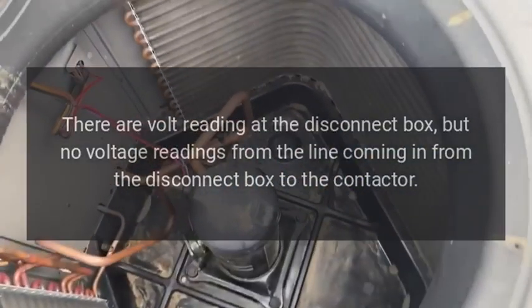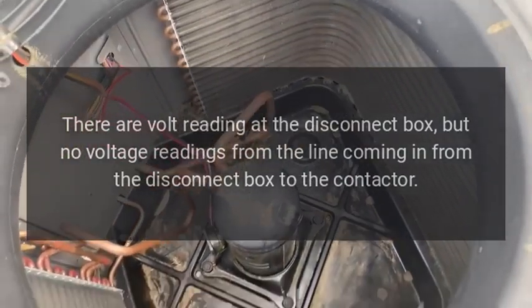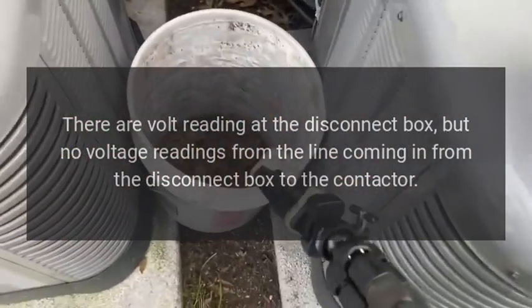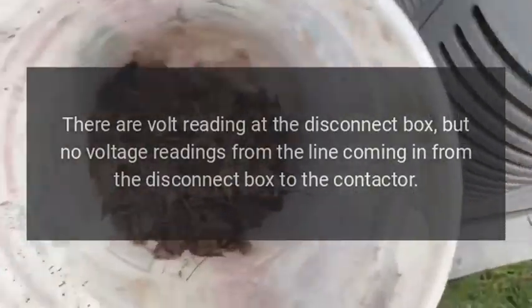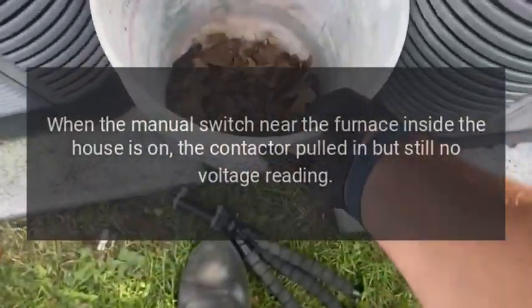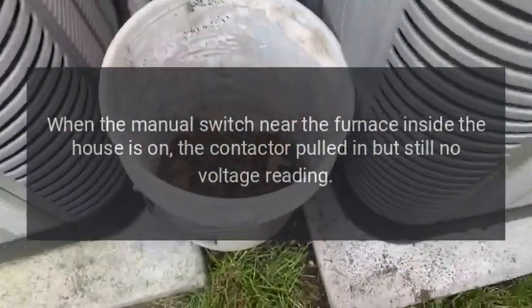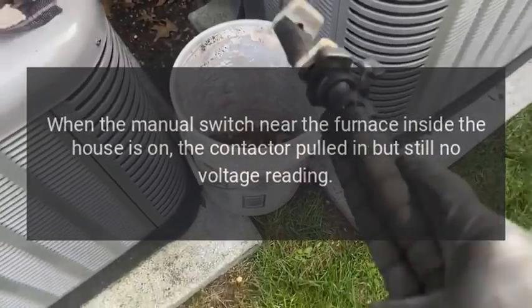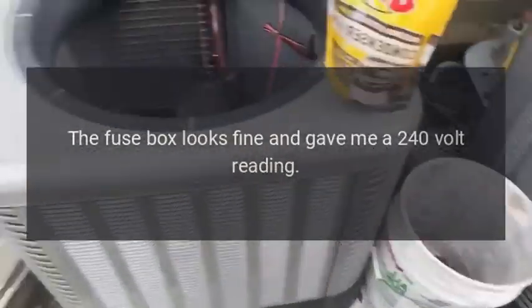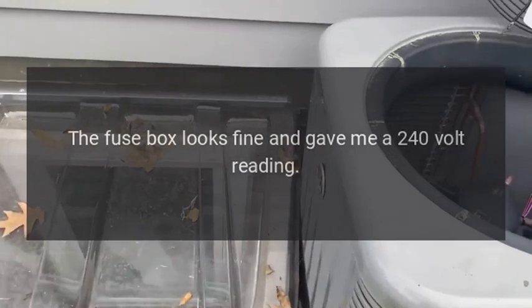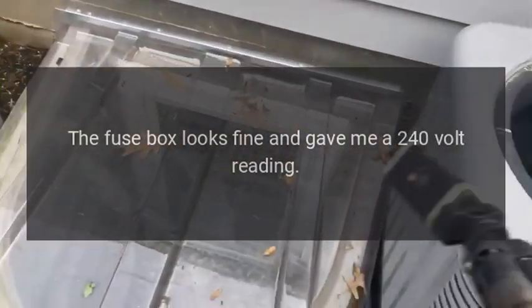Still no good. There are volt readings at the disconnect box, but no voltage readings from the line coming in from the disconnect box to the contactor. When the manual switch near the furnace inside the house is on, the contactor pulls in but still no voltage reading. The fuse box looks fine and gave me a 240 volt reading.